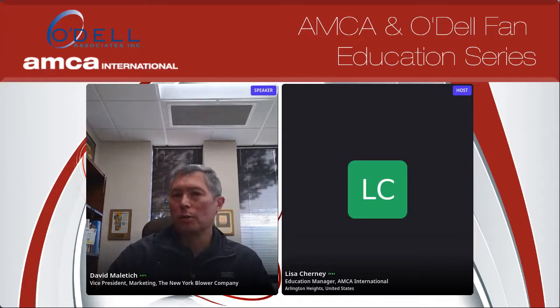You'll see in the corkscrew portion of the videos that my experience is inlet ductwork considerations are way more subjective than discharge. Discharge is relatively easy, and those rules are pretty solid rules to follow. But on the inlet side, turbulent air, especially circulating air, stuff that's coming off of a cyclone or some device that creates a spin, I've seen go 300 feet down a piece of duct and just never stop. And that's because you have two vortex creating devices, you have whatever's creating it, and you also have the wheel.